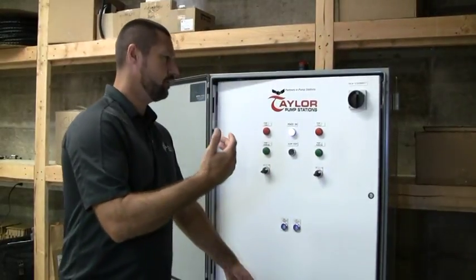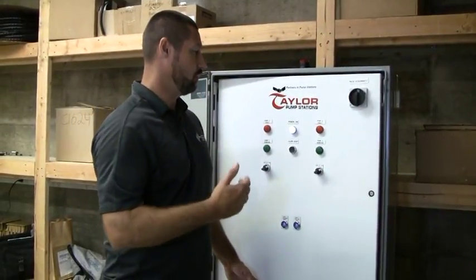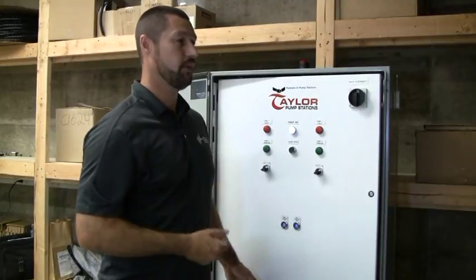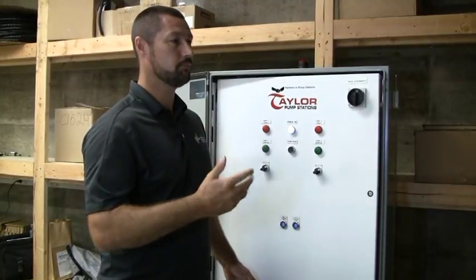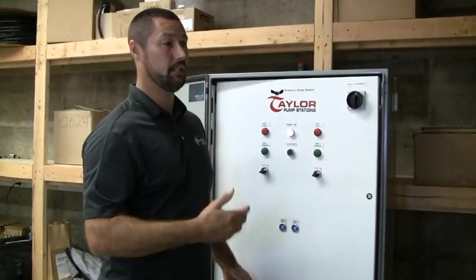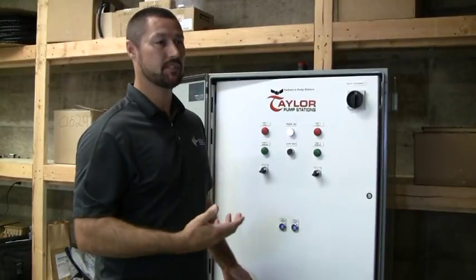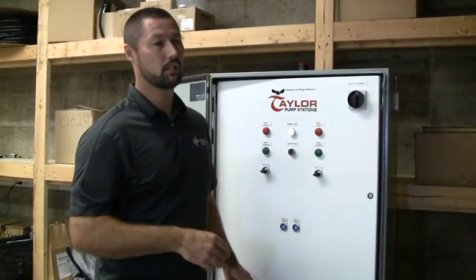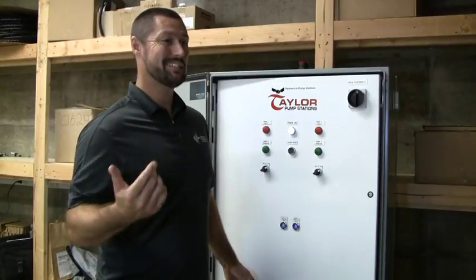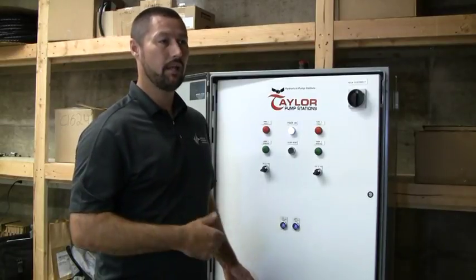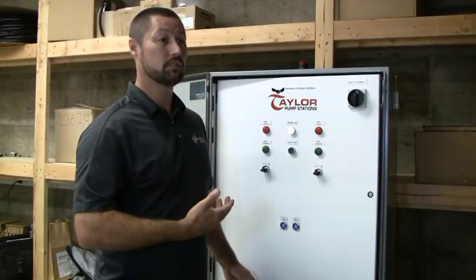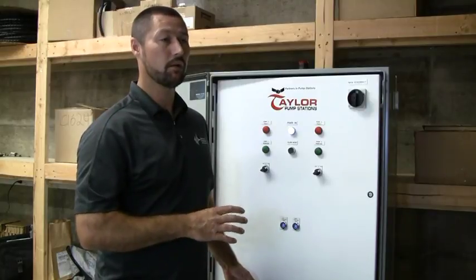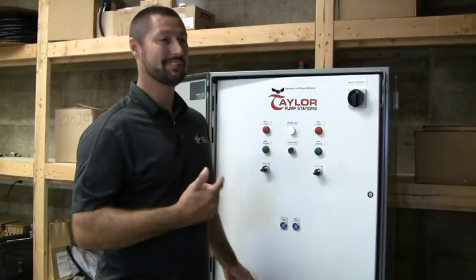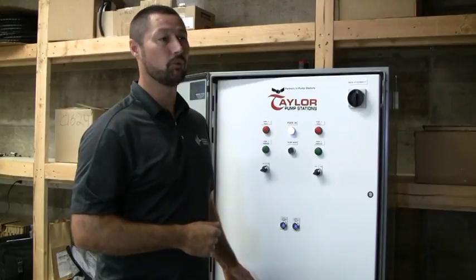In the event of a major alarm, two pumps fail, some system part fails and it can't fix itself and it can't physically run, an audible alarm is going to come on, it's going to say, hey, someone needs to get here now. A flashing red light means something's wrong, but I will still work, I will find a way to pump water. An audible alarm means I need help because I can't physically move water at that point.